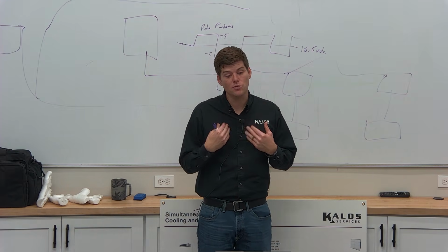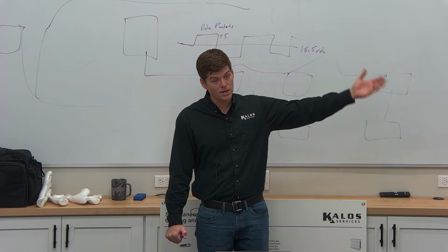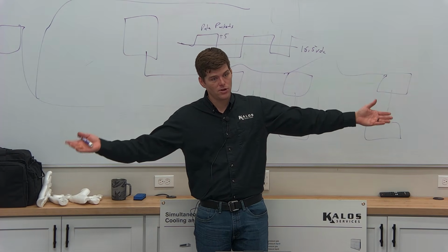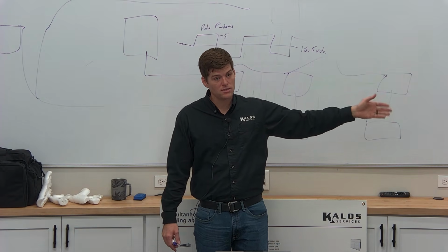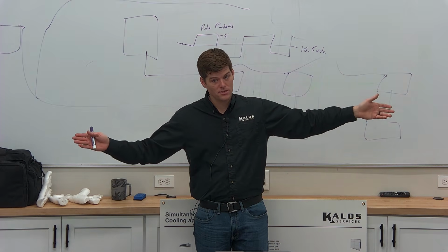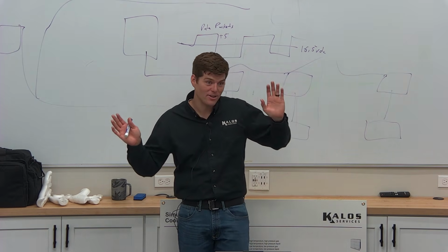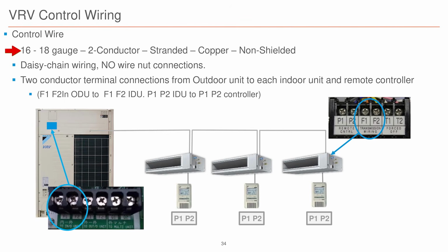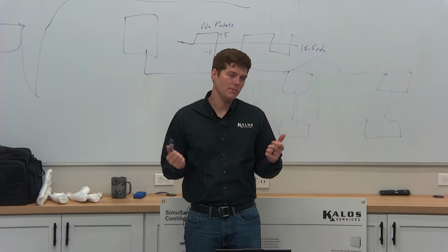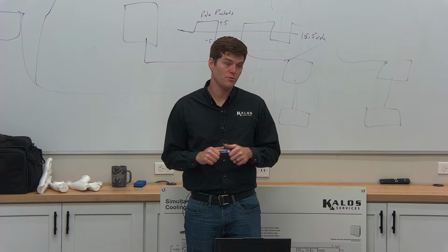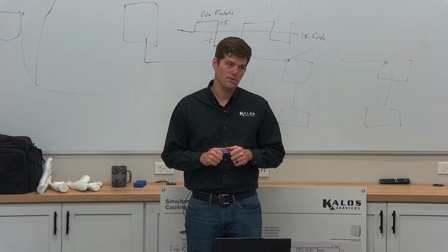I'm a firm believer in shielded wire as long as you use it correctly, and that's grounding it on one side, not both sides, and not creating an antenna. If you ground it on one side, it's good. Don't ground it on both sides. And also, don't not ground it, right? It doesn't do anything. It causes more problems than it fixes. But if you follow the rules and you use this wire, 16 to 18 gauge, 2 conductor, stranded copper, not aluminum, you can use non-shield and not have an issue. I've never seen it become an issue unless you're building it next to a radio tower, and then that's a whole other bag of cats.